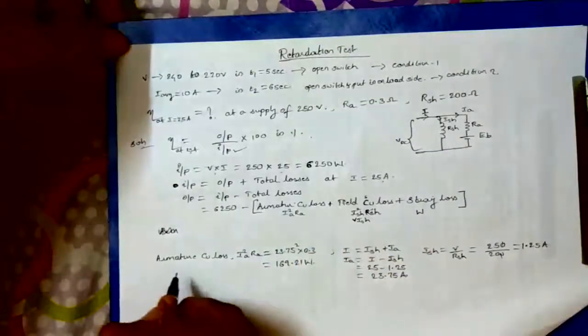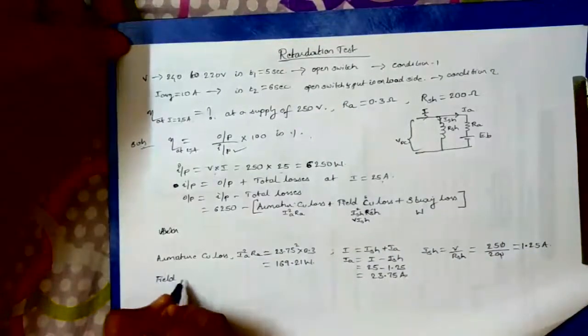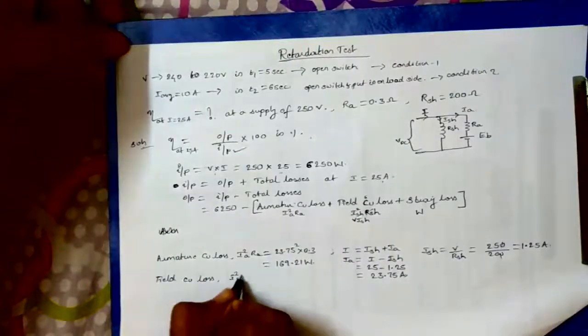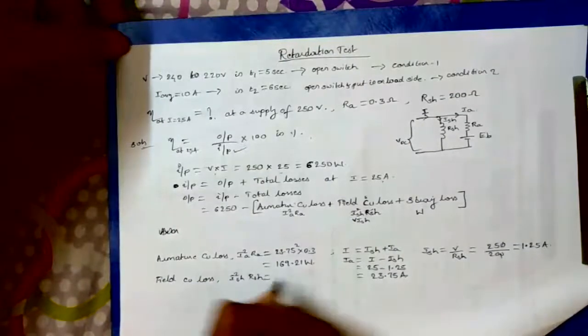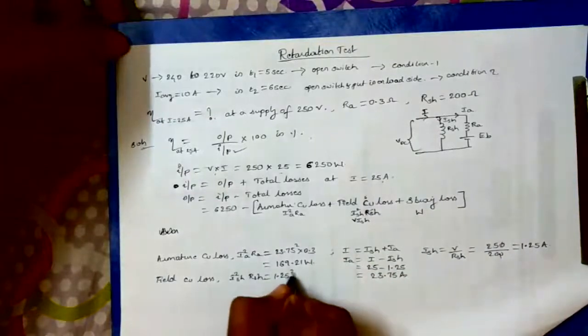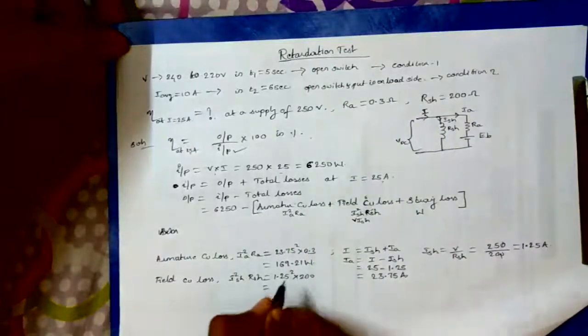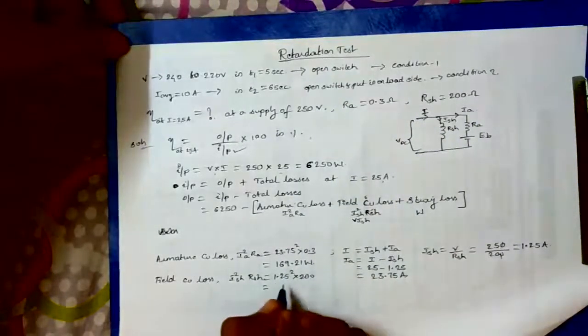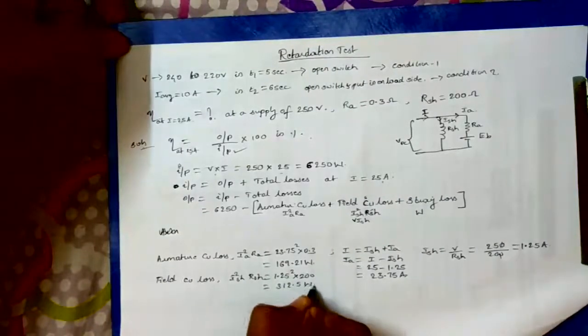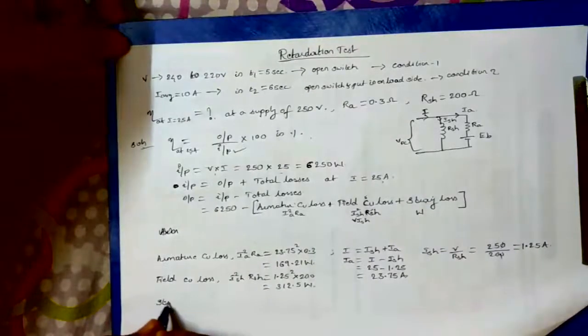Next, I squared SH into RSH, that is field copper loss. ISH is 1.25 square, RSH is 200. That will result in 312.5 watts, which is field copper loss.